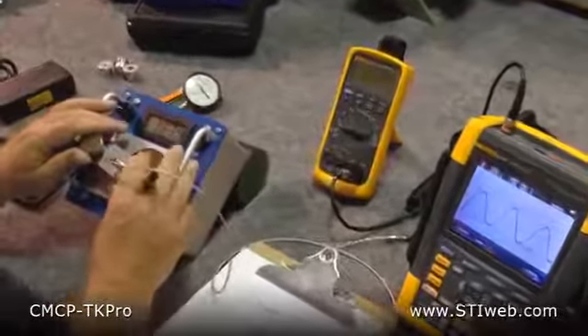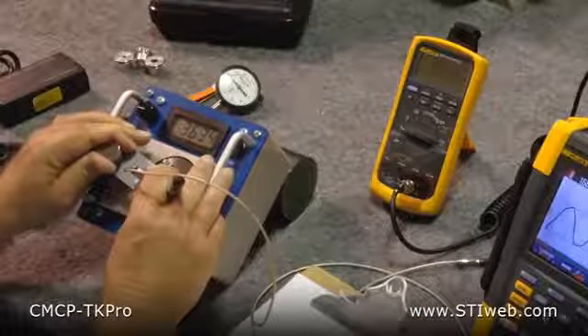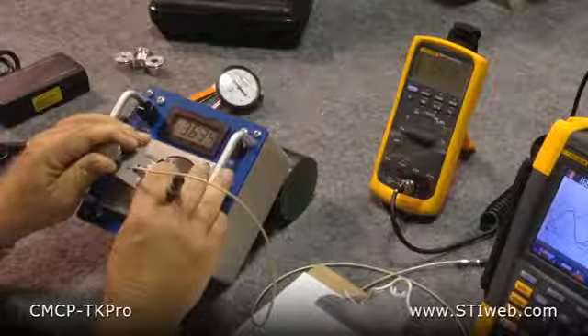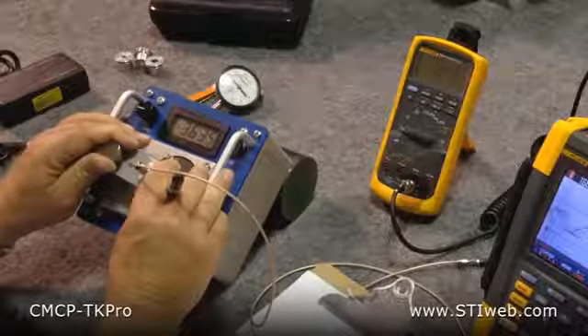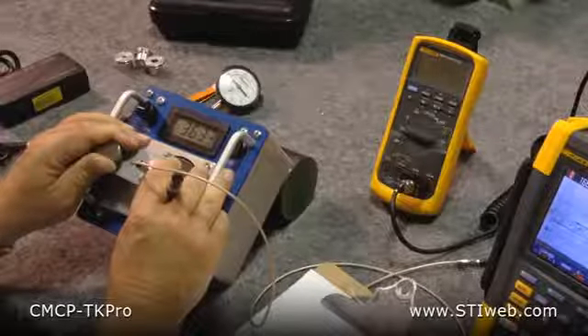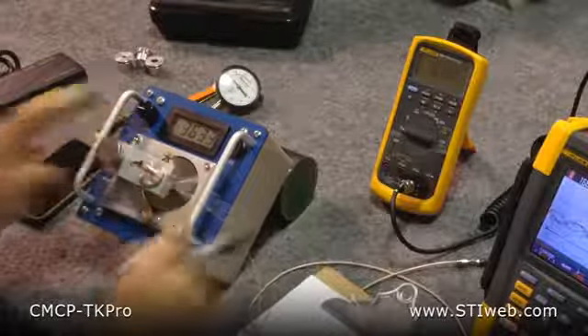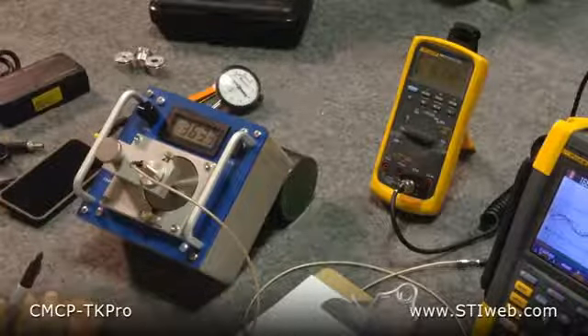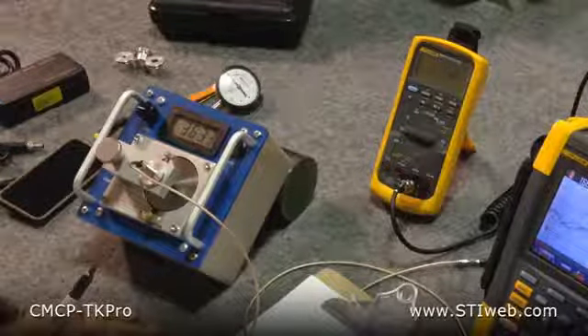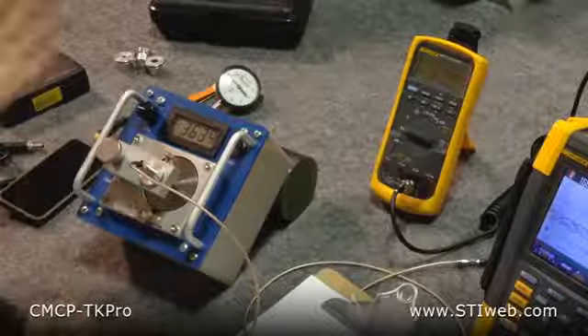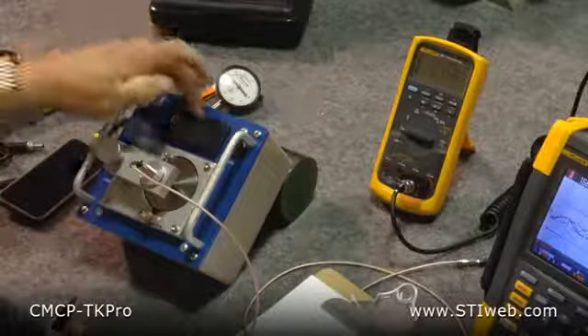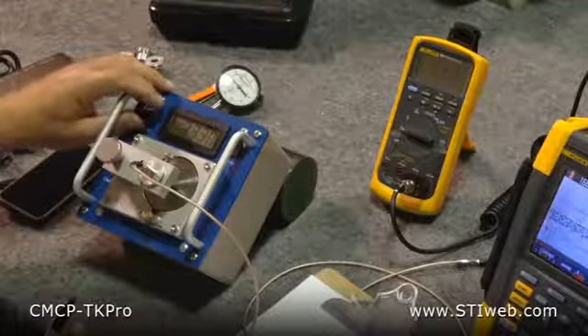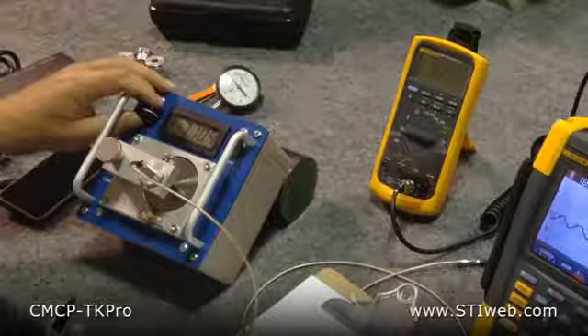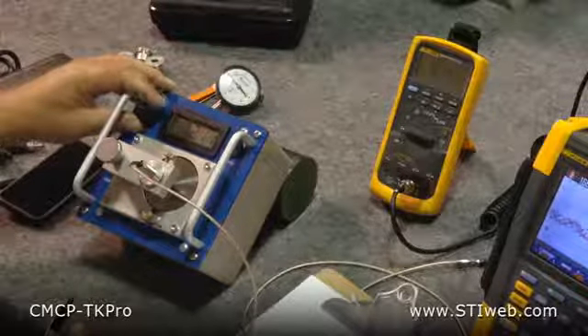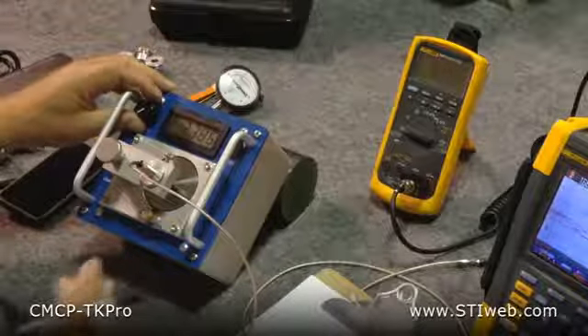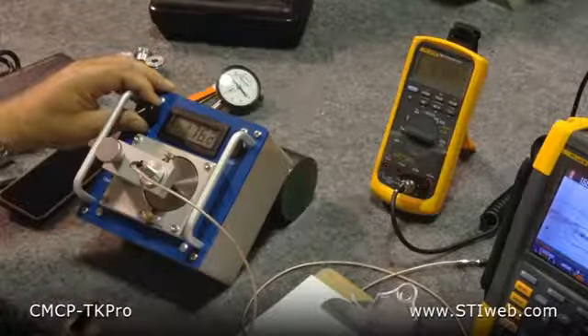And by moving this swing arm, you can see we can do any number we want. You can produce anything like 1 mil, 2 mils, all the way up to 15 mils as far as sending signal to the monitoring system. You'll notice on speed, we can adjust the speed that I've had set at approximately 3,600. We've got the ability to go up to over 7,000 RPM, and the ability to go low if you're setting up a system for a fan that runs at 200 RPM.